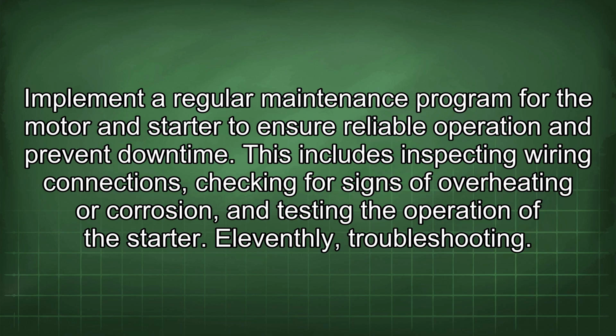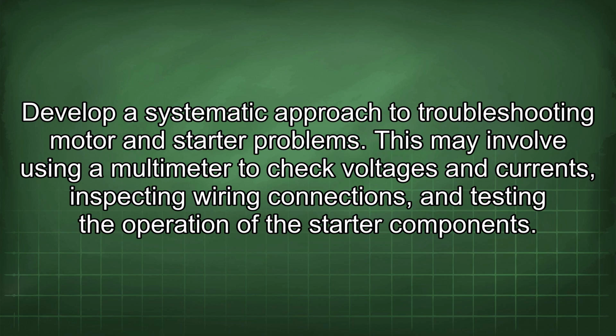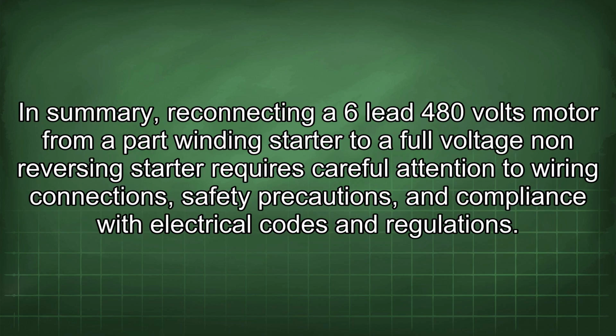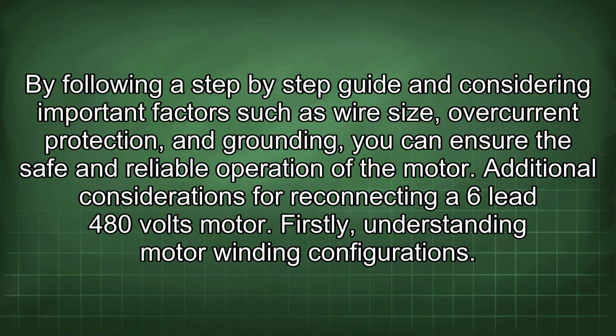11thly, troubleshooting. Develop a systematic approach to troubleshooting motor and starter problems. This may involve using a multimeter to check voltages and currents, inspecting wiring connections, and testing the operation of the starter components. In summary, reconnecting a 6-lead 480 volts motor from a part winding starter to a full voltage non-reversing starter requires careful attention to wiring connections, safety precautions, and compliance with electrical codes and regulations. By following a step-by-step guide and considering important factors such as wire size, overcurrent protection, and grounding, you can ensure the safe and reliable operation of the motor.